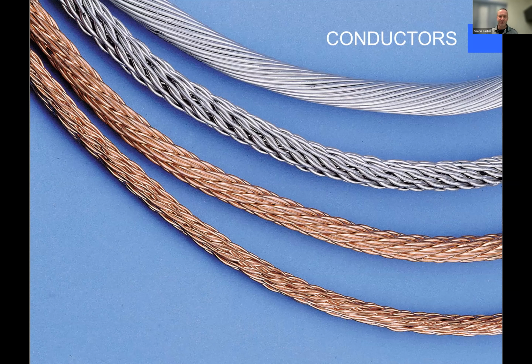Takeaway here, you see those are 4 conductors. Top conductor, class 2 aluminum. Next one down, class 1 aluminum. Next one down, class 2 copper. Next one down, class 1 copper. What do I mean by class 1 and class 2? I mean, when we're putting lightning rods on a building, we take into account the height of the structure. 23 meters is the cutoff between class 1 and class 2.